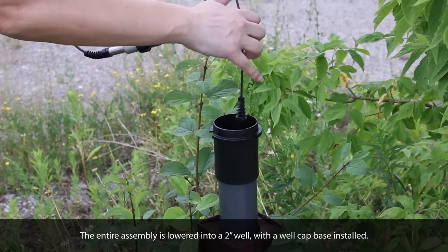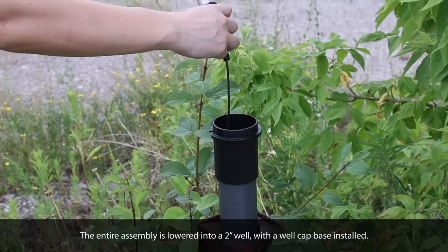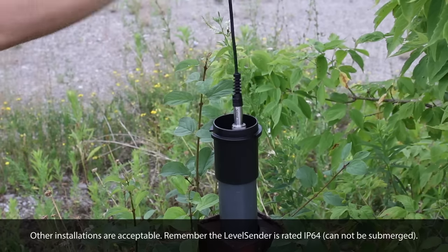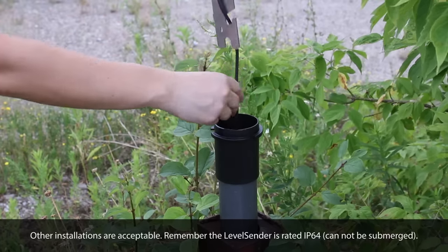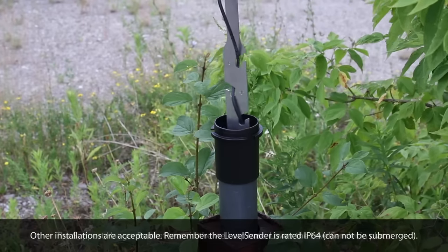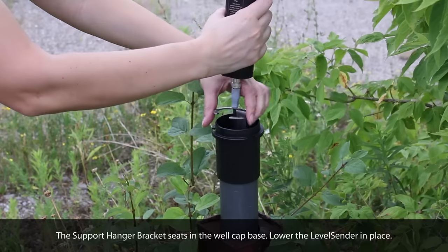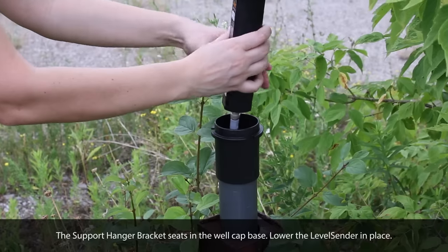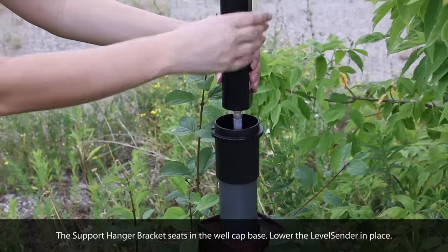The entire assembly is lowered into a 2-inch well with a well cap base installed. Other installations are acceptable, but please remember that the LevelSender is rated IP64 and cannot be submerged. The support hanger bracket seats in the well cap base. Lower the LevelSender in place.